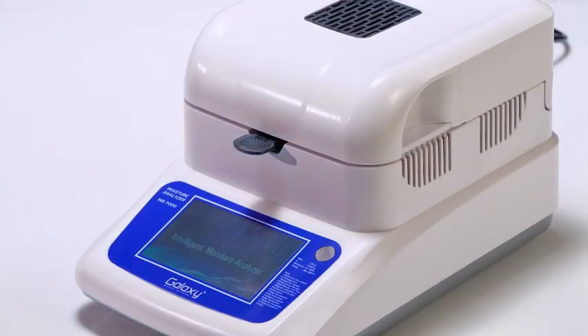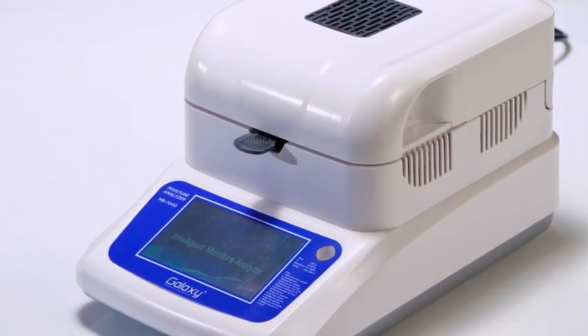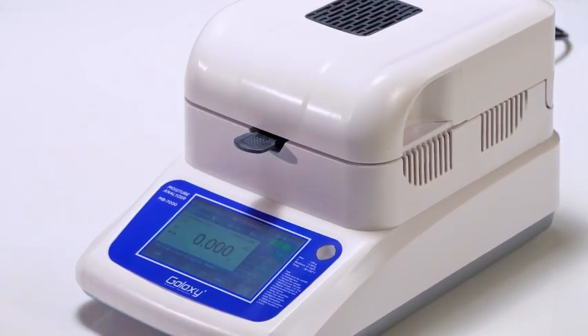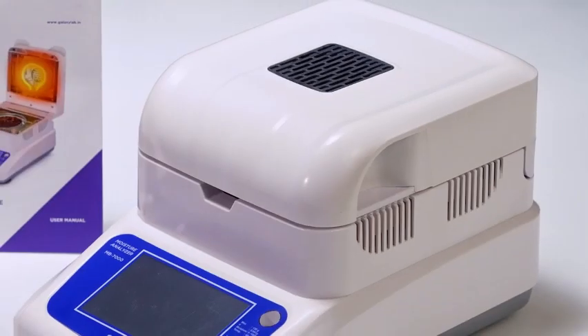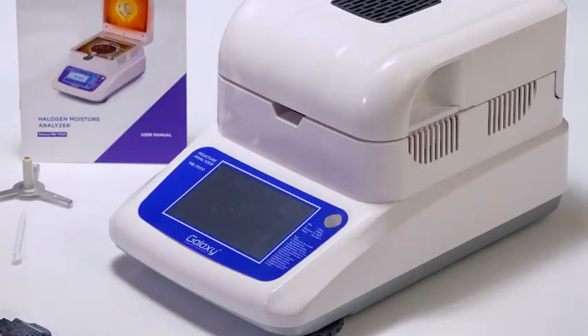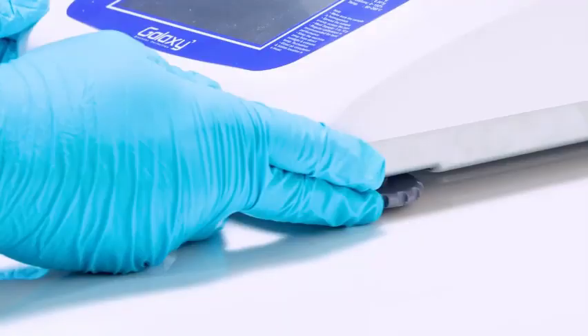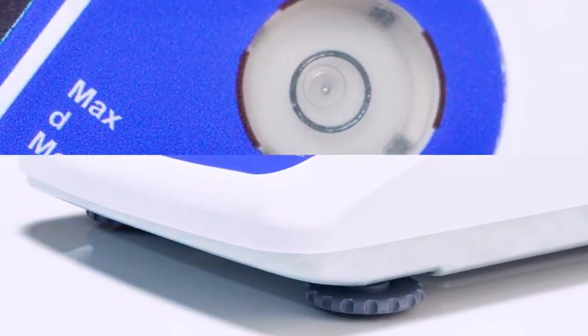First consideration is selecting the workspace. Your analytical balance needs to be placed on a steady, stable, vibration-free surface. The balance should not be used near doorways or air vents because it is sensitive enough to be affected by air. Check to see if the balance is level. Adjust the feet until The air bubble is inside the black ring.